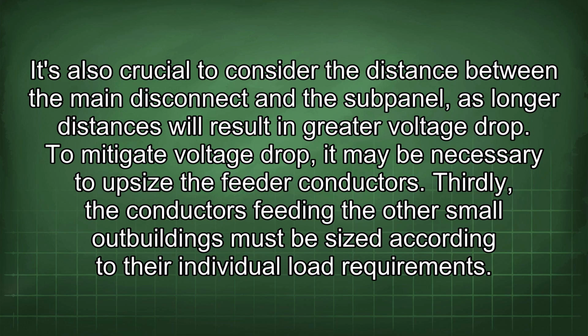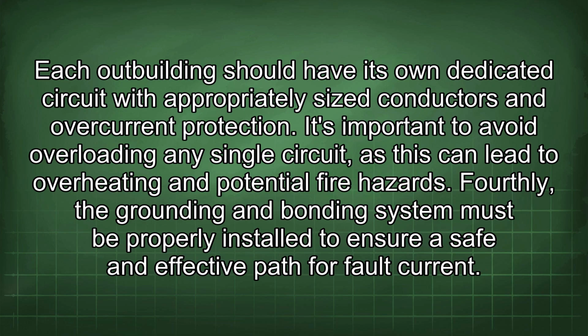Thirdly, the conductors feeding the other small outbuildings must be sized according to their individual load requirements. Each outbuilding should have its own dedicated circuit with appropriately sized conductors and overcurrent protection. It's important to avoid overloading any single circuit, as this can lead to overheating and potential fire hazards.